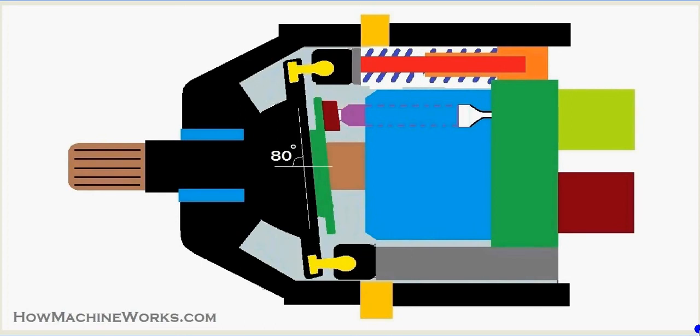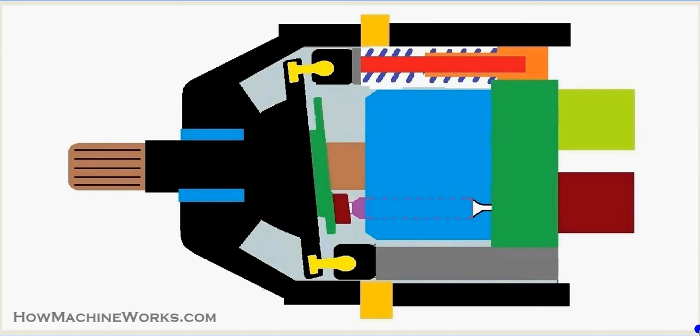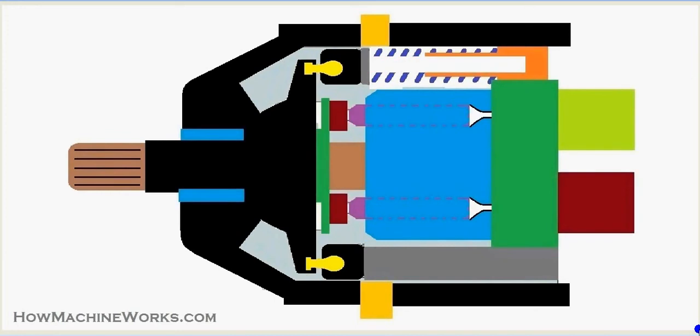As a result of that, a suction happens at the top. You can see at the top the suction happening over there, and the bottom piston you can see is actually moving towards the front because the swash plate is pushing it towards the front, so there we get the discharge. So as this particular cylinder block is rotating continuously, the pistons at the top end will create a suction and the pistons at the bottom end will create a discharge.